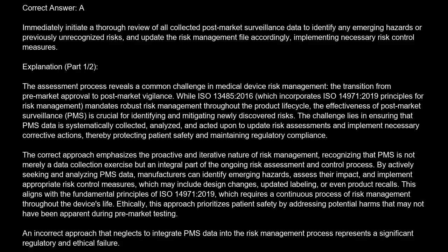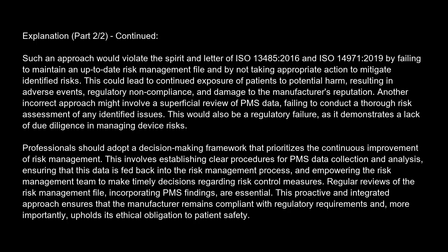An incorrect approach that neglects to integrate PMS data into the risk management process represents a significant regulatory and ethical failure. Such an approach would violate the spirit and letter of ISO 13485:2016 and ISO 14971:2019, by failing to maintain an up-to-date risk management file, and by not taking appropriate action to mitigate identified risks. This could lead to continued exposure of patients to potential harm, resulting in adverse events, regulatory noncompliance, and damage to the manufacturer's reputation. Another incorrect approach might involve a superficial review of PMS data, failing to conduct a thorough risk assessment of any identified issues. This would also be a regulatory failure, as it demonstrates a lack of due diligence in managing device risks.